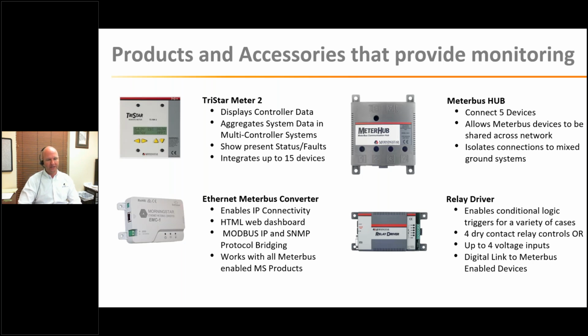Meaning we can switch 60 or even 100 amp, very large current-handling relays that not only drive power but also can signal alarms and faults. And there's 4 of those, which can also act as voltage inputs. So it's a very capable device, a very flexible one.